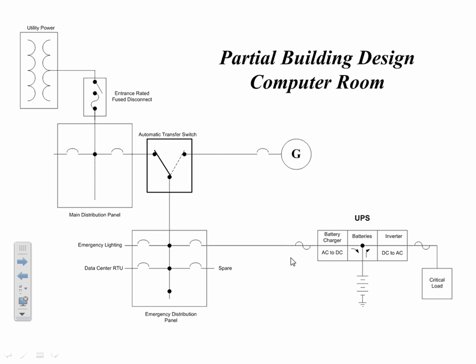In the partial building, you'll see a lot of my sketches are included in this particular one line. We'll take it from the position of going through the utility all the way to the critical load here. Up here we have utility power coming in. Here's the transformer that comes in through an entrance rated fuse disconnect or some kind of service entrance device into the main distribution panel. We've already done a sizing of how big our critical load and other stuff we're running is. So that is taken off and fed to a transfer switch that is watching utility power right here.